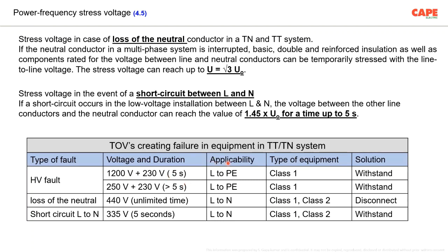Please note that this is applicable to between line to PE, line to earth. Loss of neutral is between line to neutral up to 440 volt can happen for an unlimited time. Of course, this unlimited time, it depends. It is number one applicable for a public electricity distribution system. You have to report the problem to the electricity board. Somebody may come after an hour or probably after 2 days to rectify the mistake. That is why I put unlimited time.